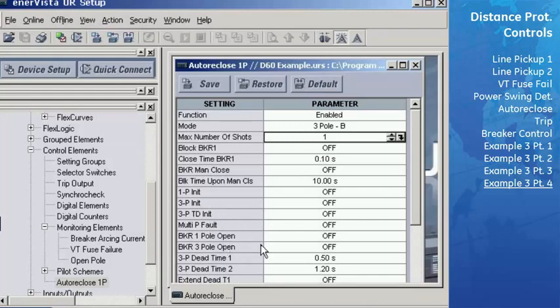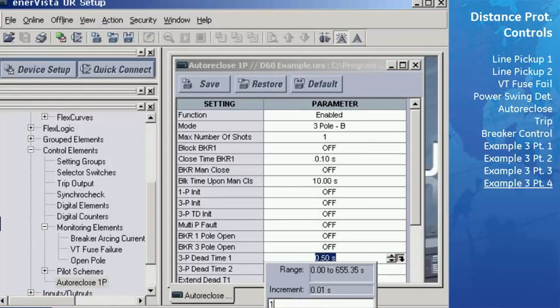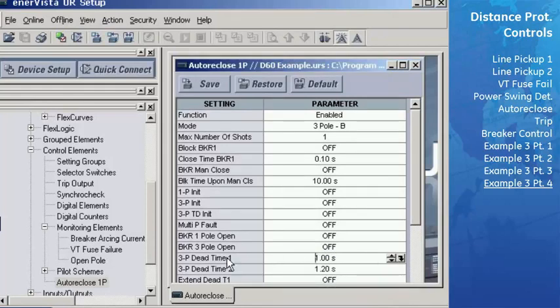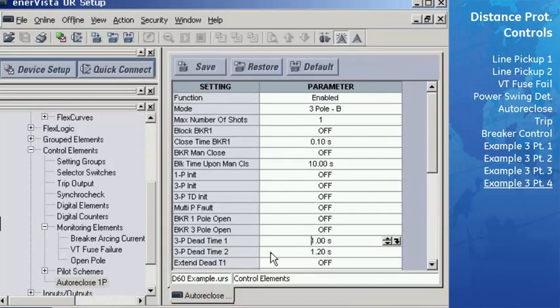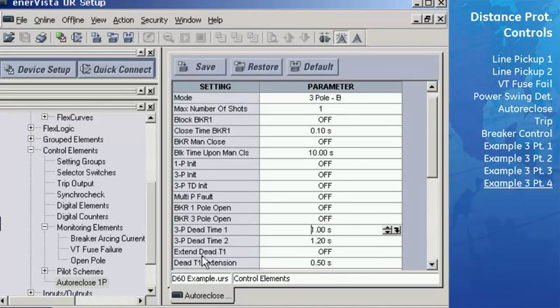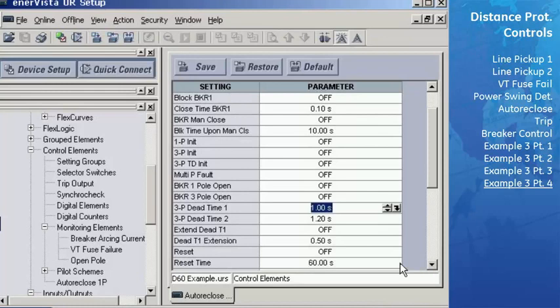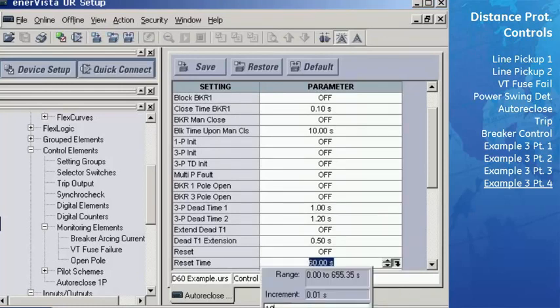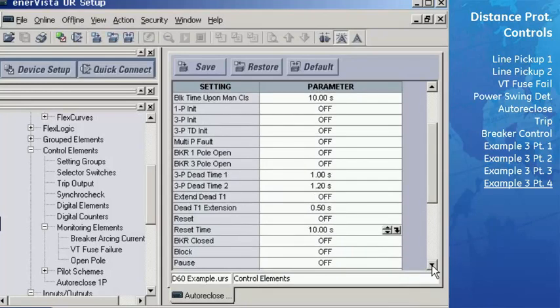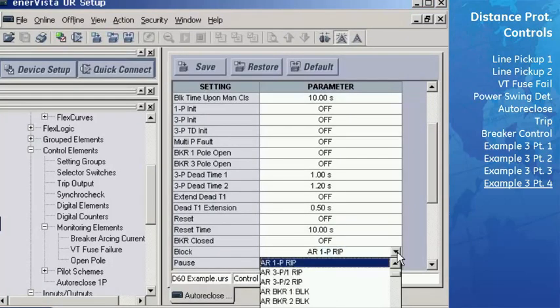Set the 3-pole dead time to 1 second, representing the dead time before the first reclose shot will commence. The 3-pole dead time 2, the dead time extender, and the reset won't be used for this example. Change the reset time to 10 seconds, which is more realistic for our 1-shot reclose of 1 second. We now need to block the recloser if the auto reclose enabled contact input signal is off. Therefore, set the block field to Auto Reclose Enabled Off, or H8C.